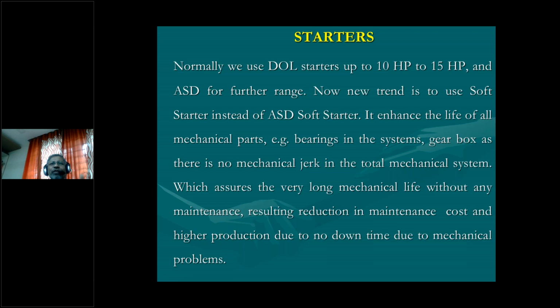So the energy concept is a very, very wide spectrum. It depends upon how we look at this subject. For this usage of soft starters in particular applications, we are always using soft starters and getting fantastic results. I will give one example. In our starch industry, we have star dryers with a standard 100 HP motor. They have gearboxes, and there is always a maintenance problem in that gearbox, after particular months or particular hours, to change the gear, bevel, everything. But after these systems, the maintenance became obsolete.